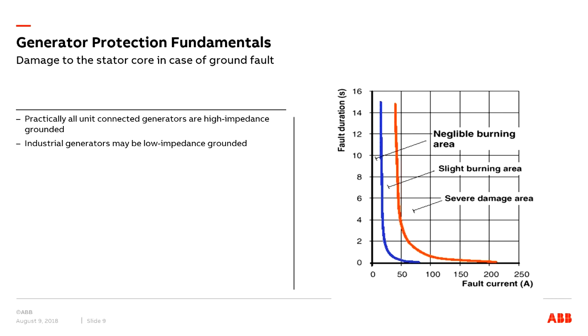So here you can see a plot to indicate the severity of the damage which can occur to the stator in case of a ground fault. If the current is limited to less than 15 amperes, the extent of damage is pretty small compared to a large fault current. If the ground fault current is less than 15 amperes, there is negligible burning. Slightly above that, slight burning, and if it is above 50, there could be severe damage to the generator. So the grounding of a generator is very important.